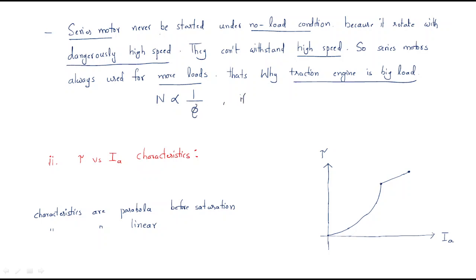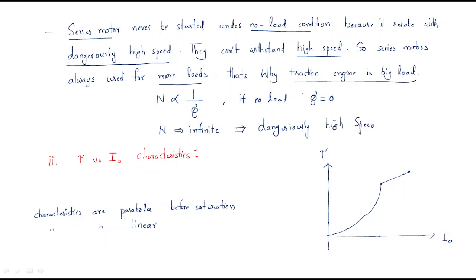If there is no load, the flux becomes zero. When flux becomes zero, speed has a chance of becoming infinite — that means dangerously high speed, and damage will occur. That is the very important reason why the DC series motor must always be started with a big load. Traction is the best example for this application.